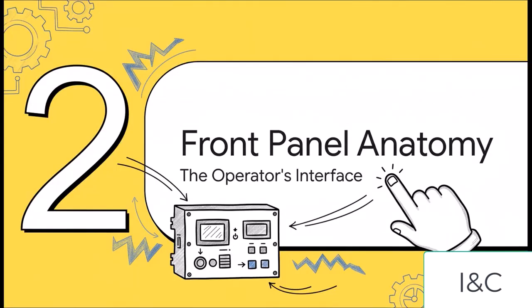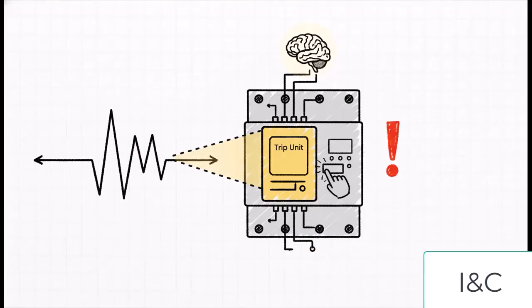Okay, so we get what they do, but how do they do it? Let's start our tour right on the front panel. This is the main interface for any operator who has to work with this thing. So the first thing you're probably going to notice is the trip unit. And this thing, this is the brains of the whole operation. It's constantly feeling the pulse of the circuit, and if it detects anything dangerous, any kind of fault, it makes the instantaneous decision to trip. It protects everything downstream. And these things are getting crazy advanced. Some of the modern ones even have touchscreens.